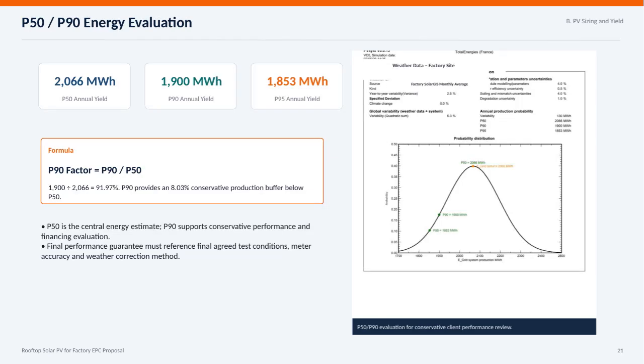Here we have the P50 and P90 energy evaluation for the rooftop solar PV system proposed for the factory EPC project. The P50 value represents the central estimate of annual energy yield, which in this case is 2,066 MWh. The P90 value is more conservative, set at 1,900 MWh, meaning it accounts for uncertainties and ensures the system will produce at least this much energy 90% of the time. The P90 factor here is about 91.97%, which means there's an 8.03% buffer below the P50 estimate to provide a conservative performance outlook. This is crucial for evaluating financial risk and performance guarantees.